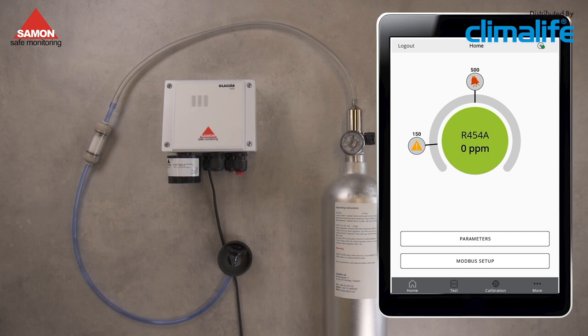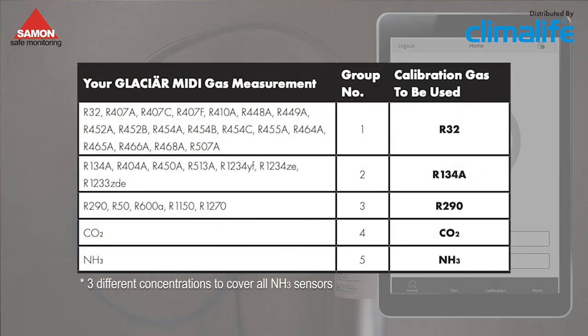Thanks to Samon's intuitive and streamlined gas grouping system, you can calibrate using fewer gas types, improving efficiency and reducing the need for extensive gas inventory. You can find a list of defined and approved calibration gases in the Glacier MIDI manual or refer to the list currently displayed on screen. In this example, the gas detector is configured to monitor R454A, which belongs to Group 1. R32 shall be used as the calibration gas for this group.